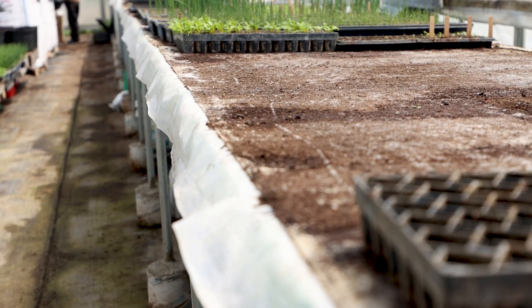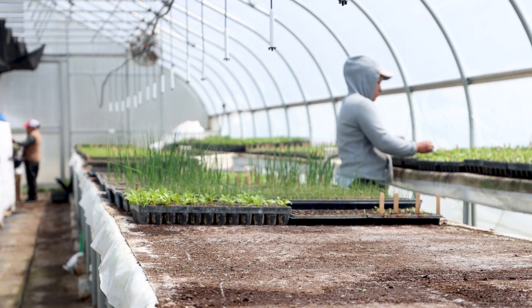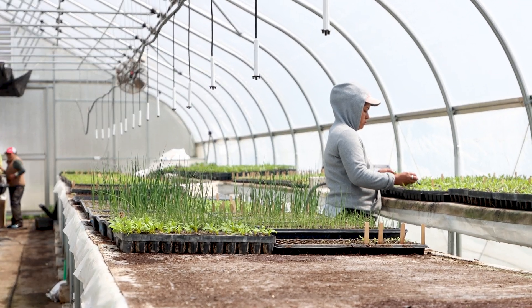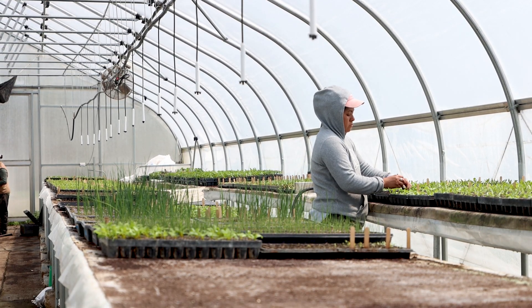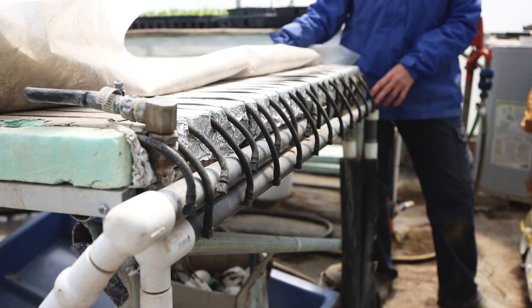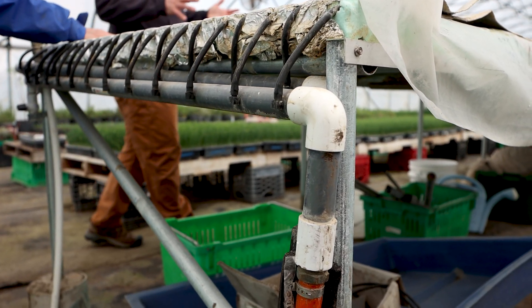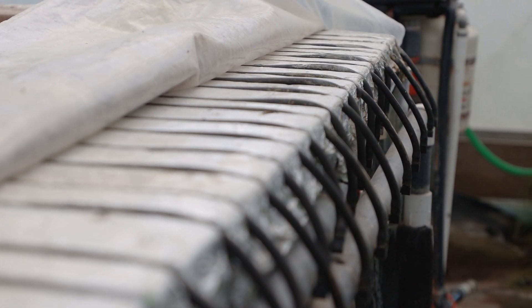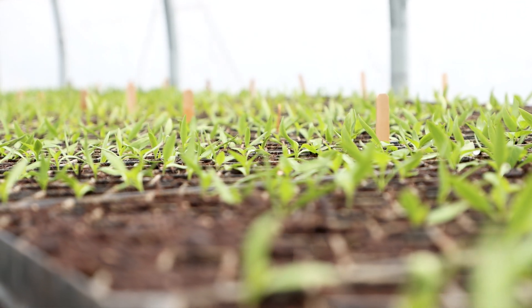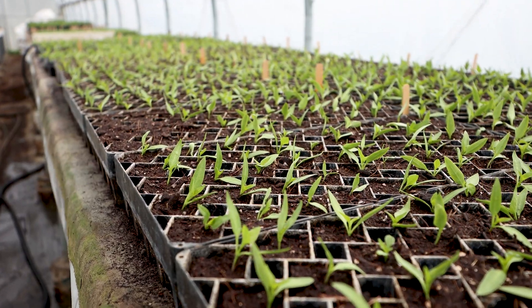This system works really well supporting these two benches, which are about 66 feet long. One heater comes into two manifolds, and we're able to shut one bench off and heat only the other. The manifolds have an outgoing and a return. We use the Delta-T Solutions system — they come pre-drilled and barbed fittings just snap in. The tubing comes on a long roll you cut to length. For the investment of what I can do with these two 66-foot benches, it totally pays for itself.